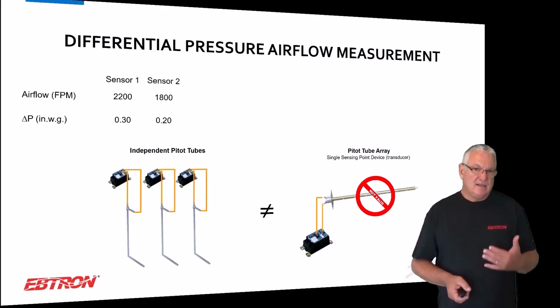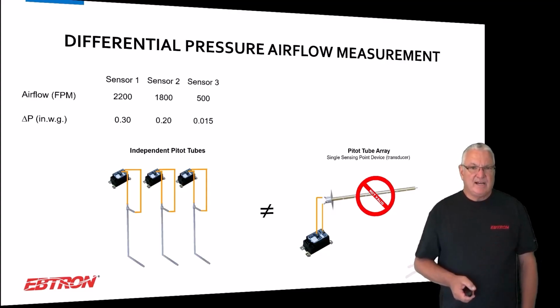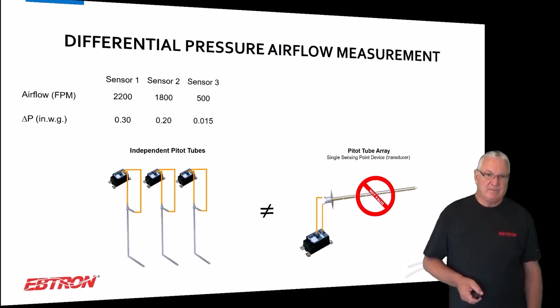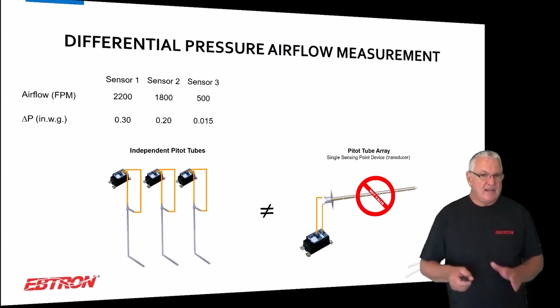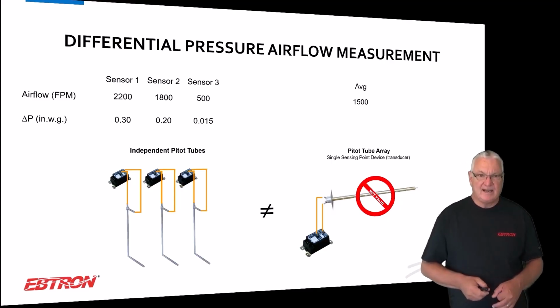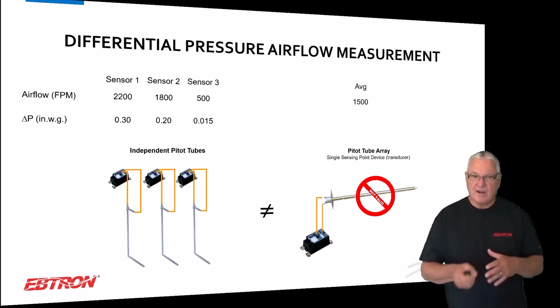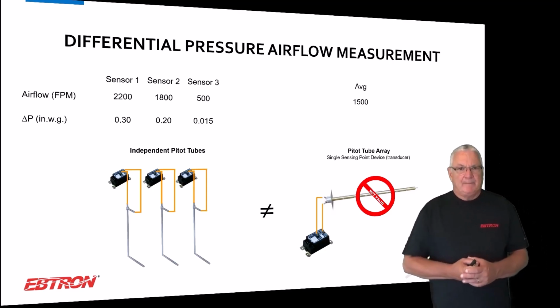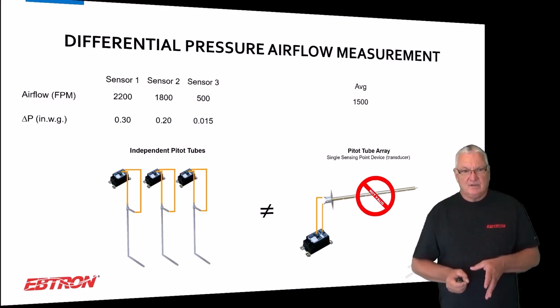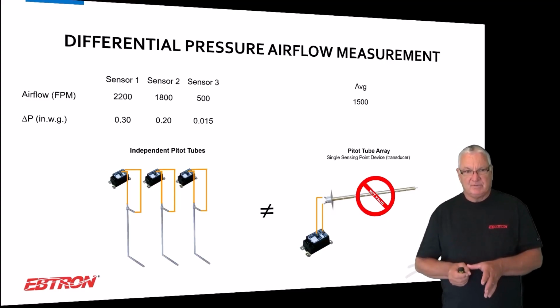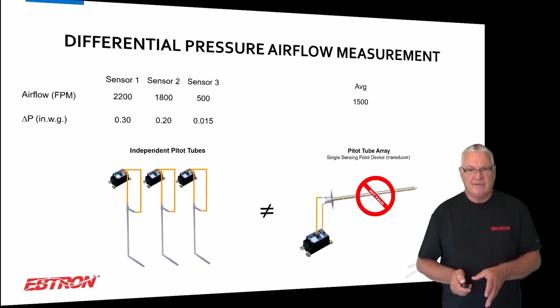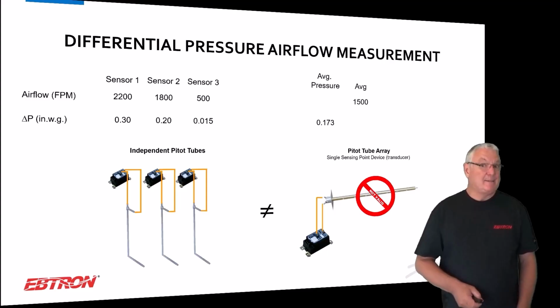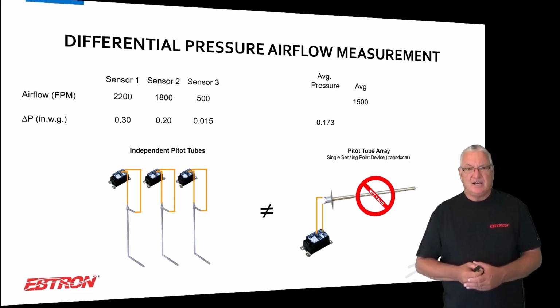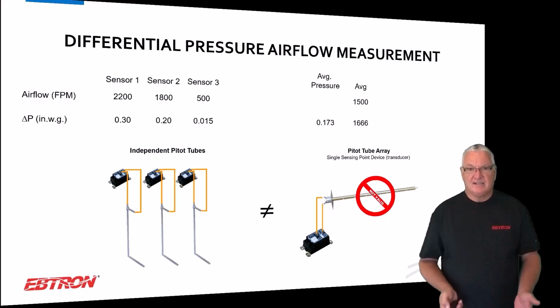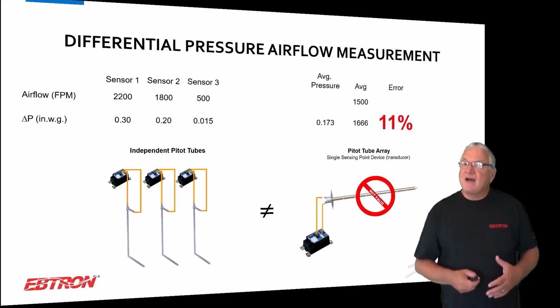Here we could be downstream of an unveined elbow. So we have very high velocity on one side of the duct, 2,200 feet per minute on the left sensor, and 500 on the right sensor. If everything was perfect, you would have calculated the average of this example to be 1,500 feet per minute if there was no error in any of the measurement. Yet the best that the averaging arrays can do is give you the average of those 3 velocity pressures, so the 0.3, 0.2 and 0.015, which is 0.173, and that's the best it can do. If you calculate the velocity based on that 0.173, you get 1666. It's 11% off, and that's just math.